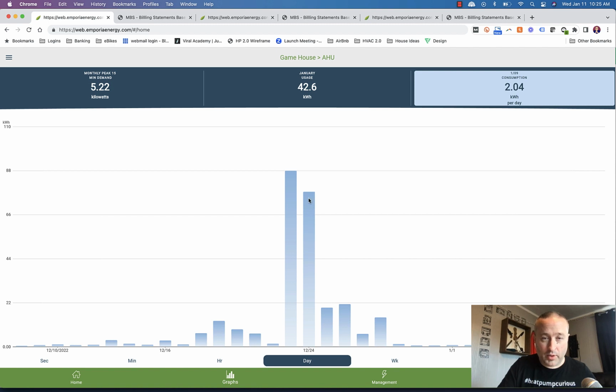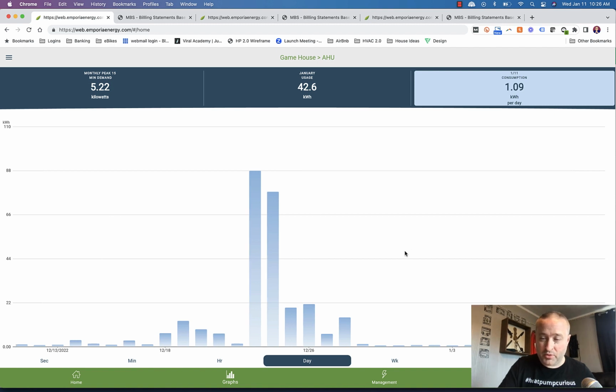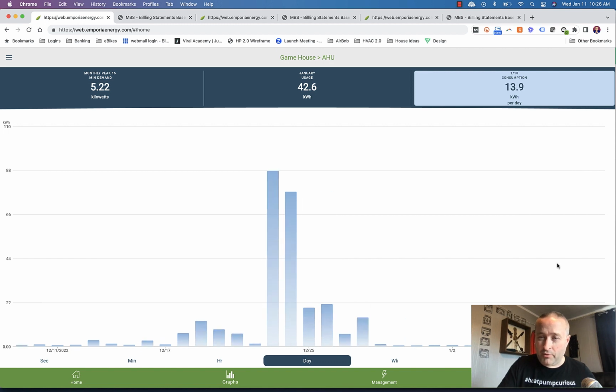And then more like 75 the day after. So you can see there's been a little bit of resistance getting hit, but not a whole heck of a lot. Those were the bad days because it was cold. Like yesterday, it wasn't that cold, but if you ask for a big temperature difference and it's kind of cold, oftentimes you'll engage resistance and it'll do it. So I used 14 kilowatt hours yesterday. So this is what that looks like. So this was an ugly day.